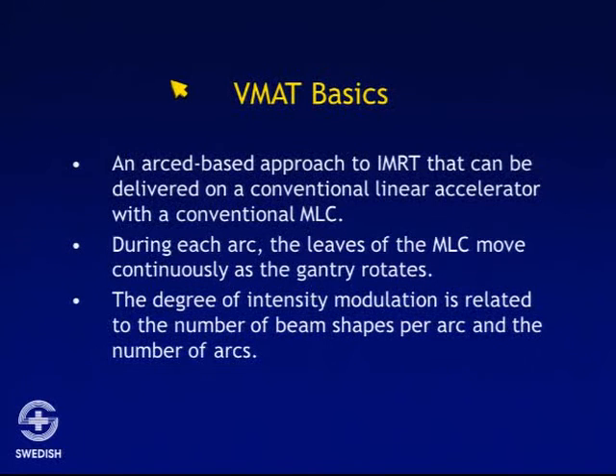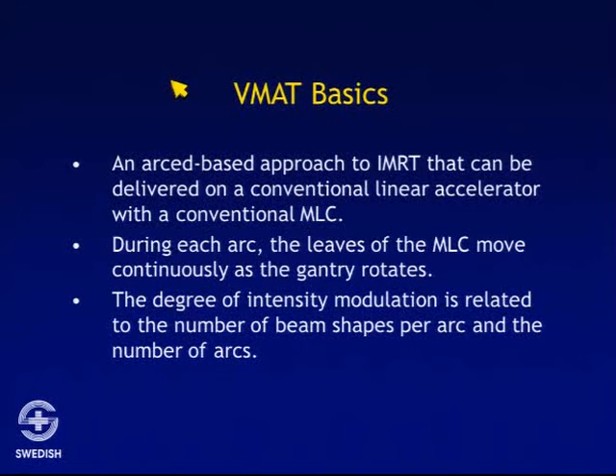The basics of IMAT or VMAT is an arc-based approach to IMRT that can be delivered on a conventional linear accelerator with a conventional multi-leaf collimator. During each arc, the leaves of the MLC move continuously as the gantry rotates. The degree of intensity modulation is related to the number of beam shapes per arc and the number of arcs.